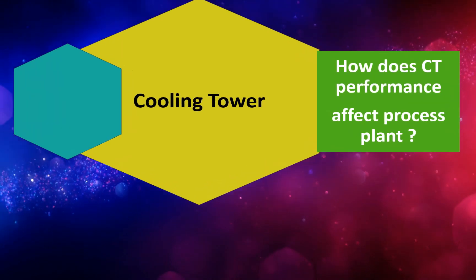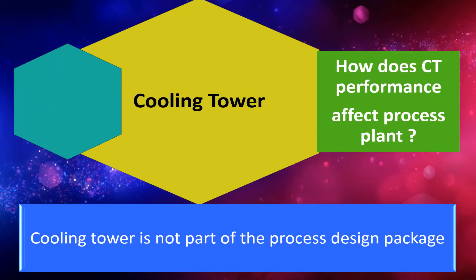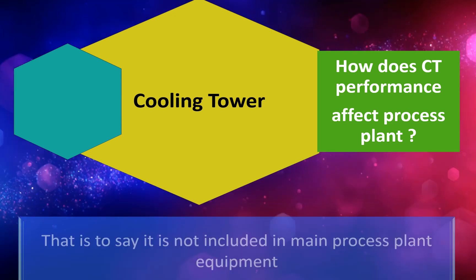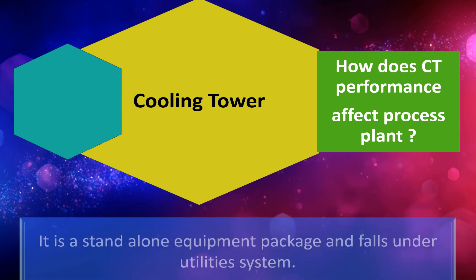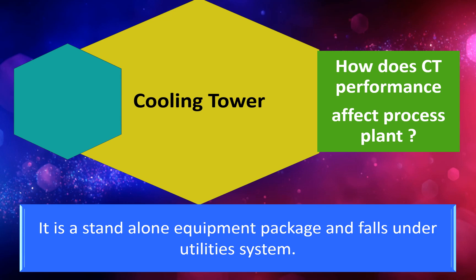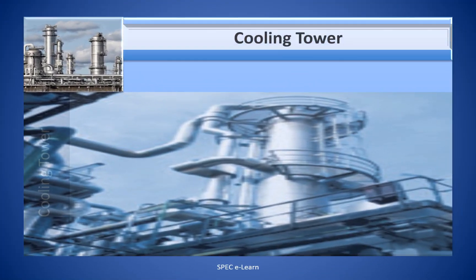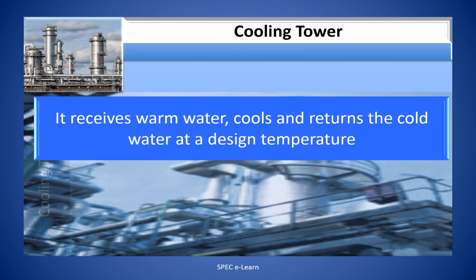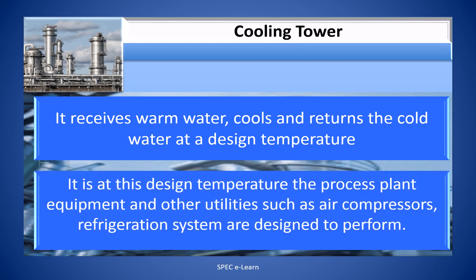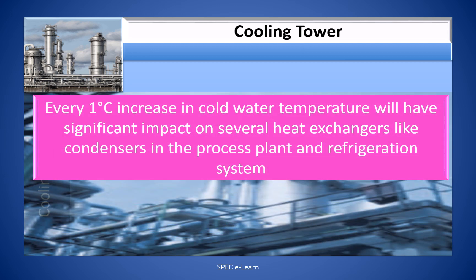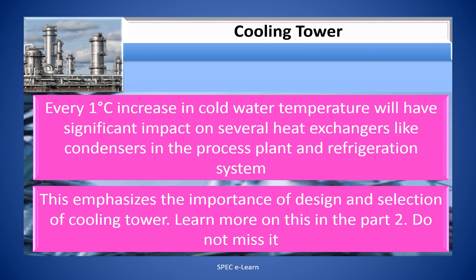How does cooling tower performance affect the process plant? Cooling tower is not part of the process design package — it is a stand-alone equipment package under the utility system, designed and supplied by the cooling tower manufacturer. It receives warm water, cools it, and returns cold water at a design temperature. Process plant equipment and utilities such as air compressors and refrigeration systems are designed to perform at this temperature. Every 1°C increase in cold water temperature has a significant impact on heat exchangers like condensers and on the refrigeration system, emphasizing the importance of proper cooling tower design and selection.